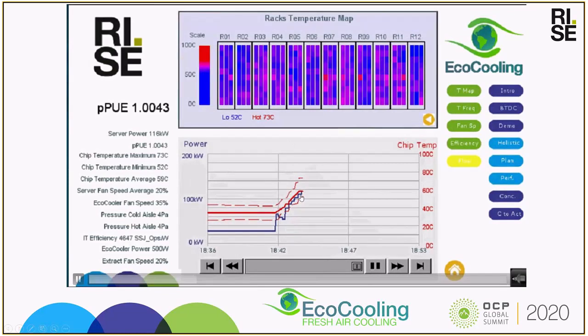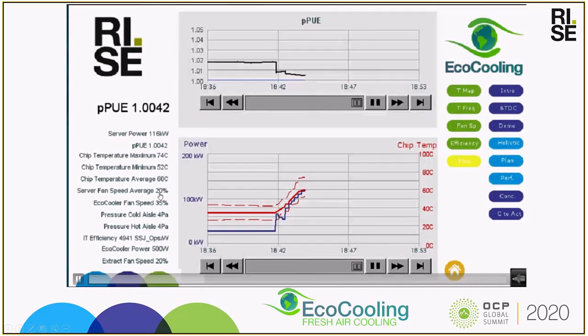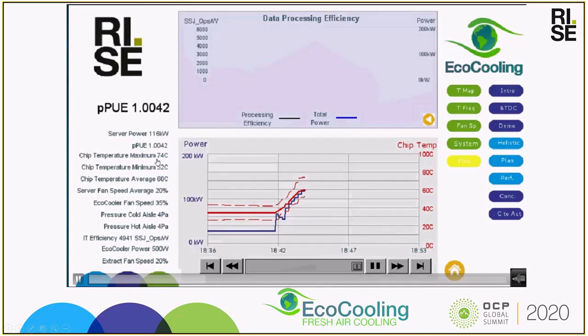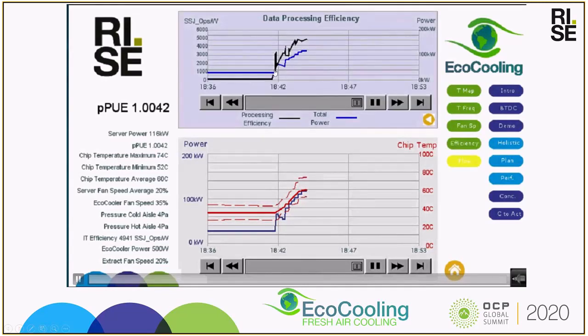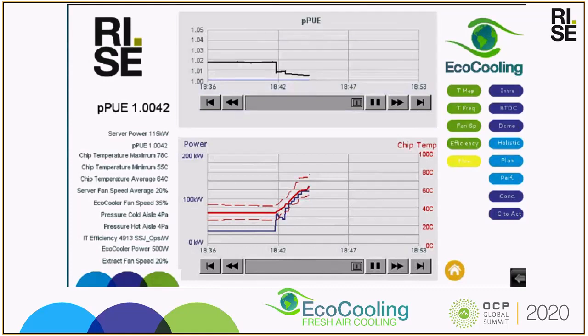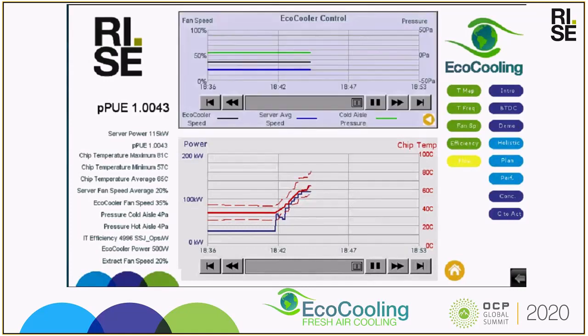As the IT power increases, you can see that the chip temperature increases here. Now the hottest temperature is 74, but the average temperature is 60 centigrade. And the calculated IT efficiency has gone up from 0 to around 5,000 server-side Java operations per second per watt of power consumed by the whole module. So we're monitoring the power of both the IT and the facility when we do that calculation.